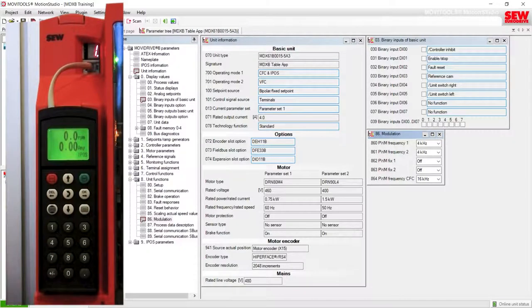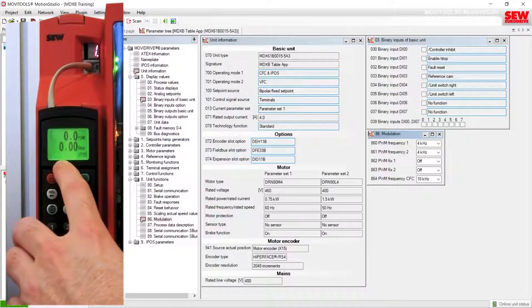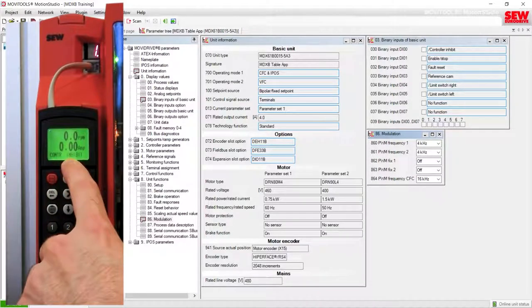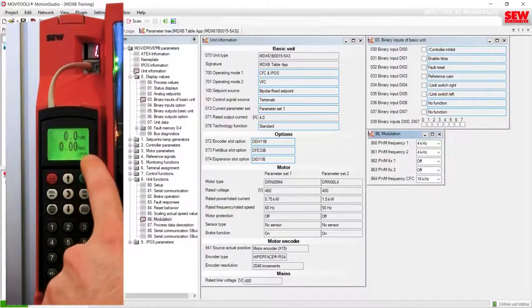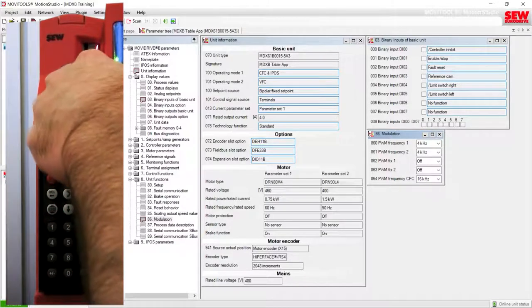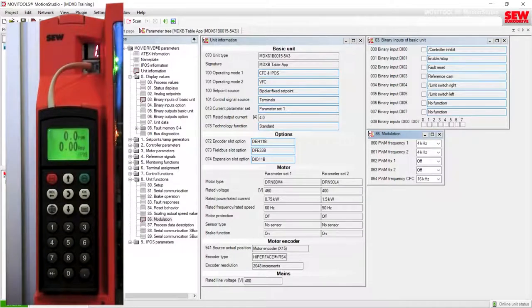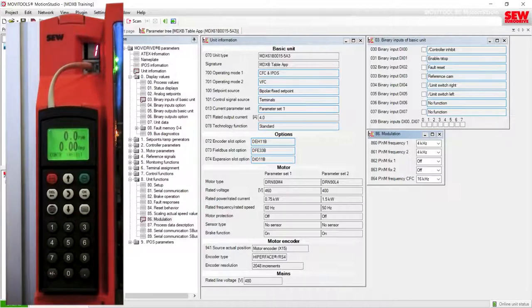It jumps us to the basic display, which is what you would see during normal operation when you are not using the keypad. Currently there is no speed on the motor and no amperage. Down here flashing, you can see it is showing controller inhibit because our DI00 input is currently turned off. You can also see IPOS appearing in the corner, which matches the red decimal in the 7-segment display, meaning there is an IPOS program loaded to this MOVIDRIVE from the previous lab activity. The number 1 on the 7-segment display also means controller inhibit.